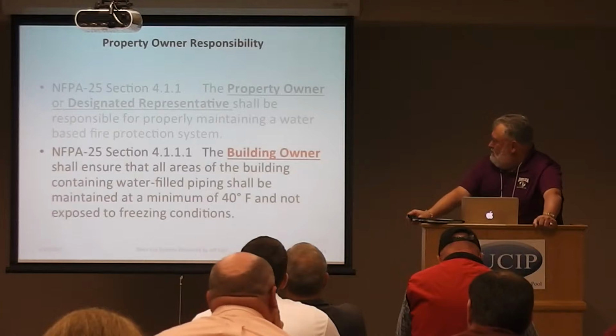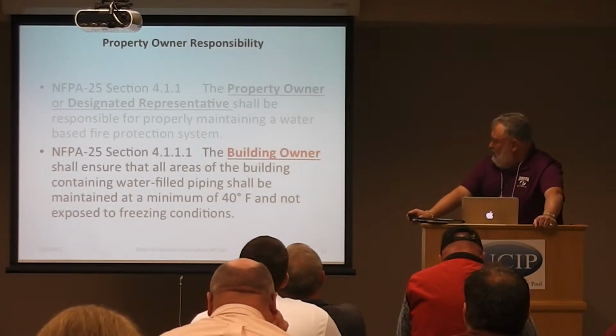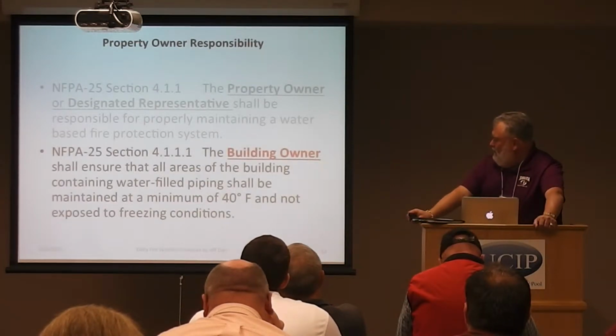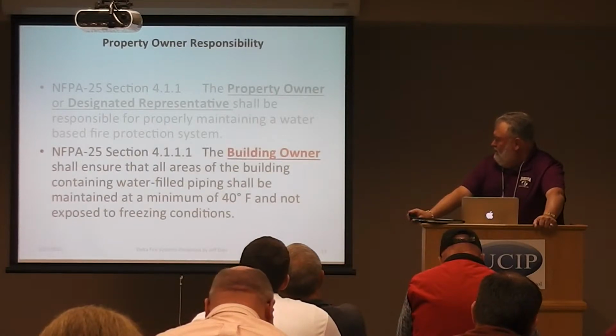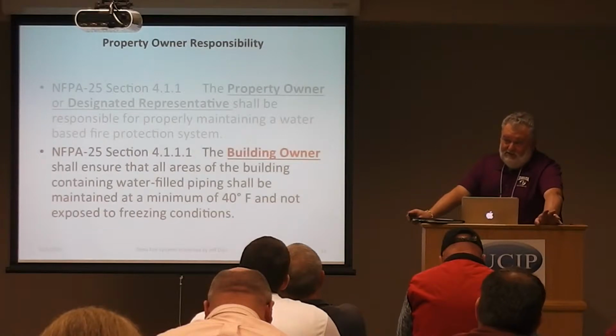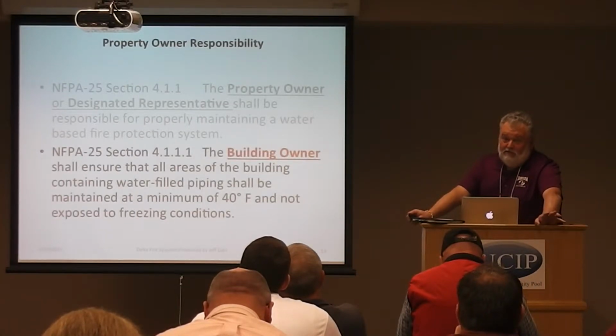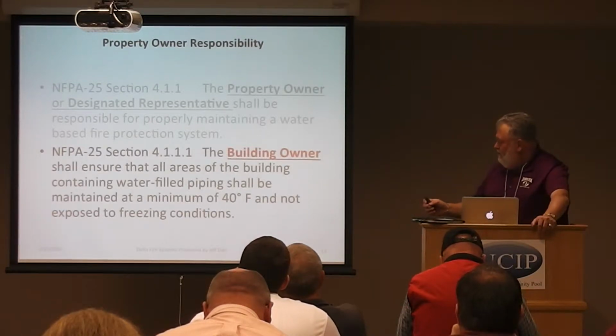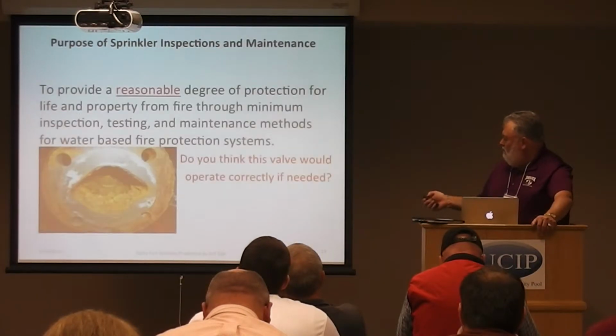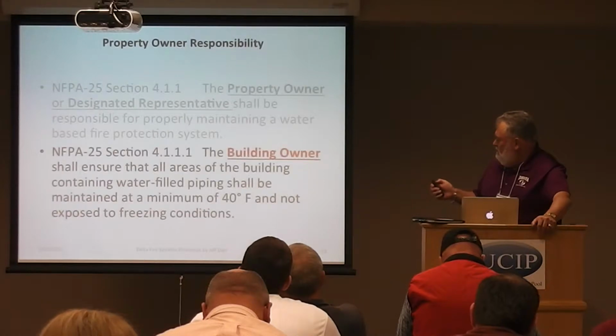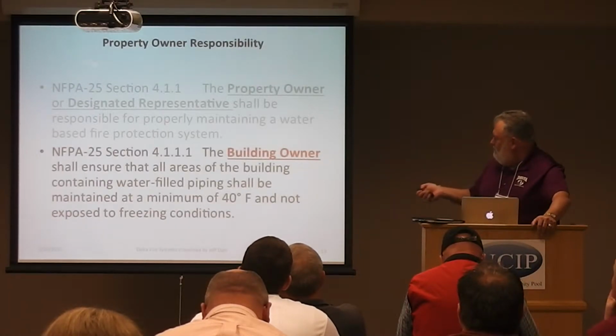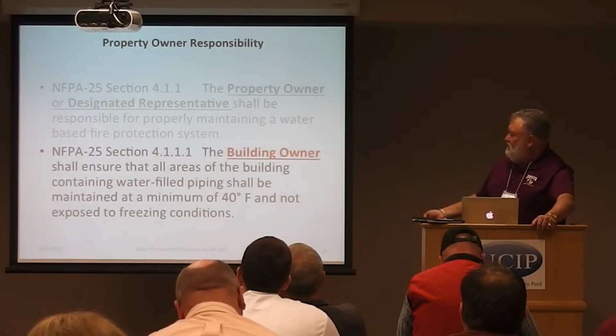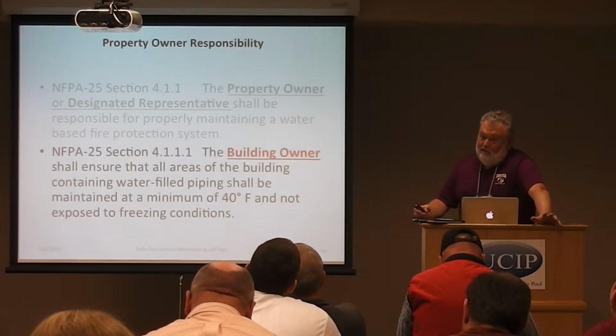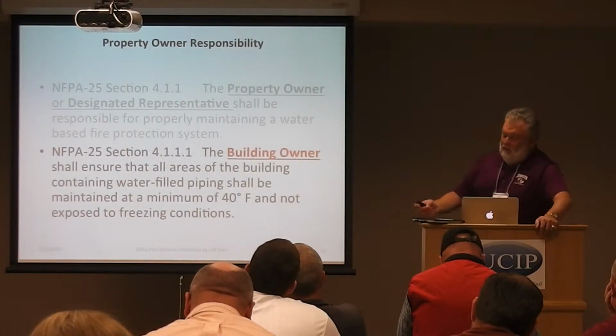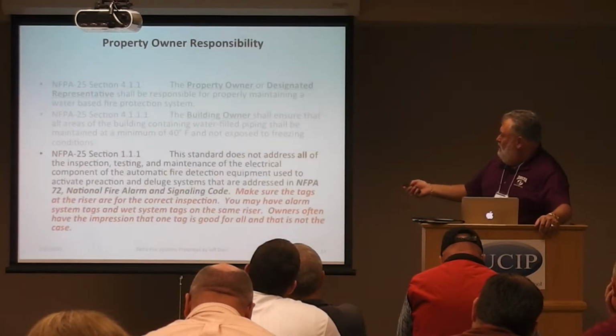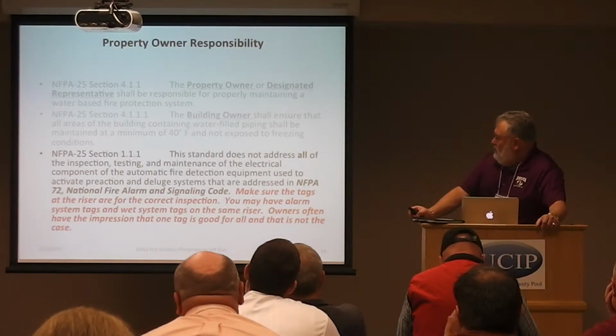That being said, under 4.1.1.1, the building owner shall ensure all areas of the building containing water-filled piping shall be maintained at a minimum of 40 degrees Fahrenheit and not exposed to freezing. There are systems out there, dry systems for instance, that you can have below zero. They're not concerned with that. They're very concerned here. I hope I get this pointer working right here. Oops, went the wrong way, excuse me. Well, I guess I'm not getting the pointer to work, but they're concerned about the 40 degrees on water systems. And I'm sure some of you have heard about antifreeze being the solution. We'll talk about that a little further on. It's really not anymore.